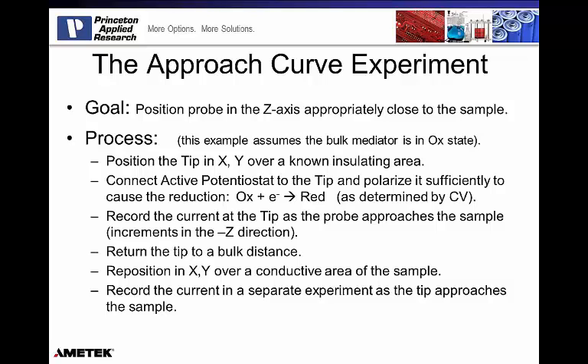But so in our 5-step process, we've done a CV on the probe, and we did that primarily to determine the voltages that we're going to be using in imaging. That also gives us an idea of the amount of current to expect from a bulk response with the probe. Then I moved on and did a macro electrode CV, or a sample CV, and that fundamentally just proves the sample connection, and that I have the bulk response I'm looking for out of the probe itself. So the next 2 experiments I'm going to do are very similar. They're approach curves. In fact, it's the exact same experiment. It's just whether I'm over an insulating area or over a conducting area.